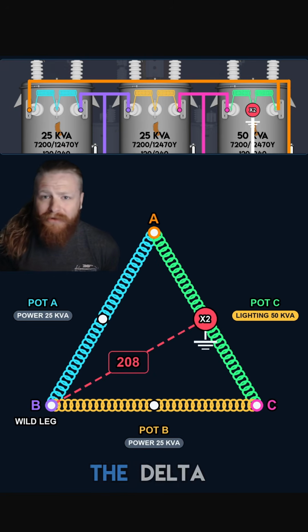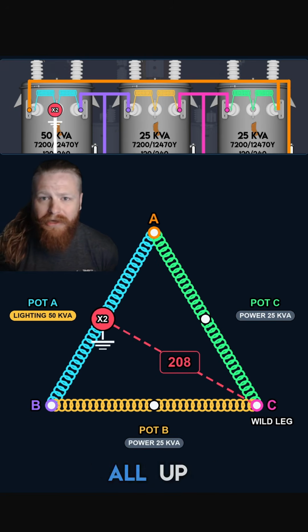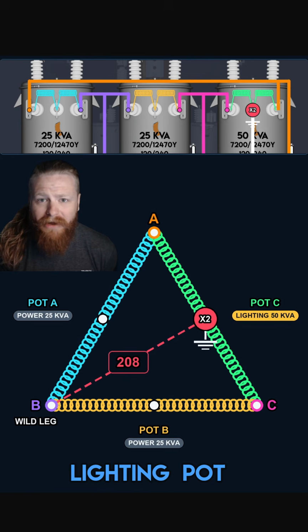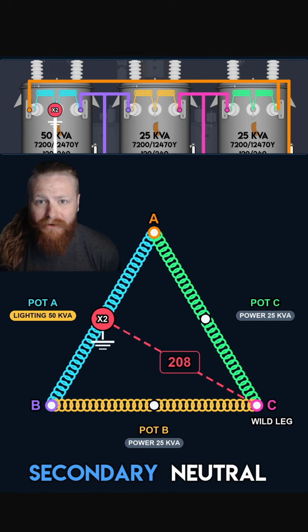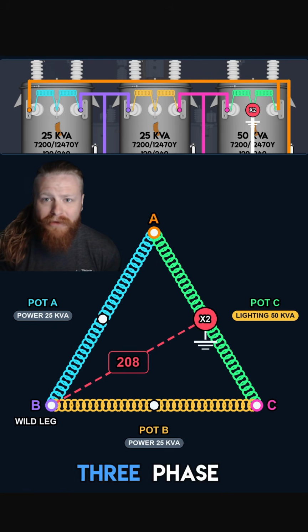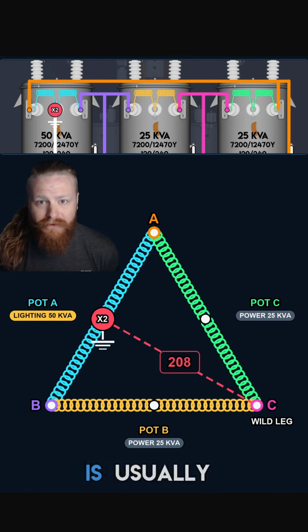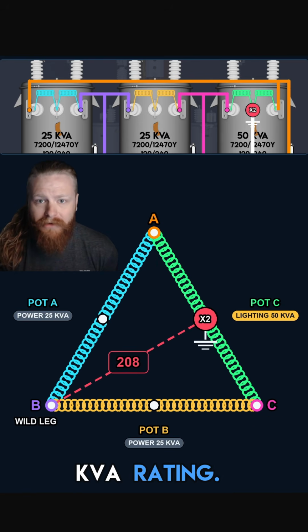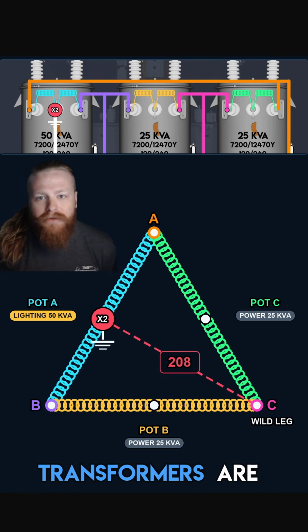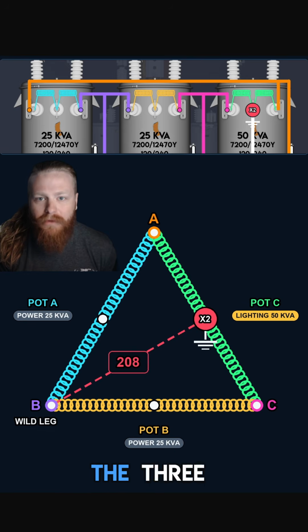We've made it this far into the delta secondary, so we might as well button it all up. Whatever pot you ground becomes your lighting pot. It carries the lighting load, and the bank's secondary neutral reference, while the other two pots share the 3-phase load. That's why the lighting pot is usually larger with a higher kVA rating. It's doing more. The other two transformers are the power pots, and they carry the 3-phase load.